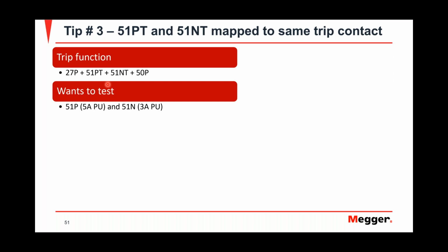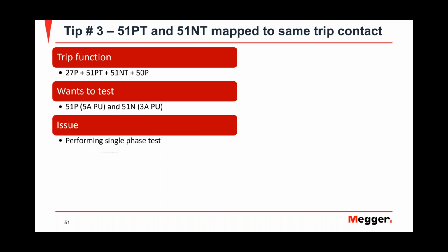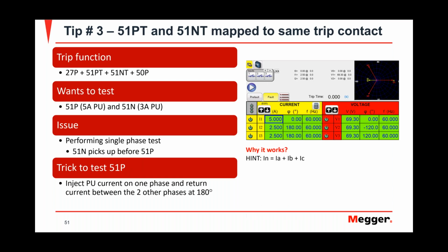On this one, what you want to do is test, and this happens a lot, 51P, your time overcurrent, that's 5 amps, but you also have a 51N at 3 amps. And you're doing a single phase test or a 3-phase test, and your 51N trips before your 51P trips. So how do you deal with that? Because you're going to inject a single phase test, and the relay is going to see it as a single phase to ground fault. It's going to see neutral current.